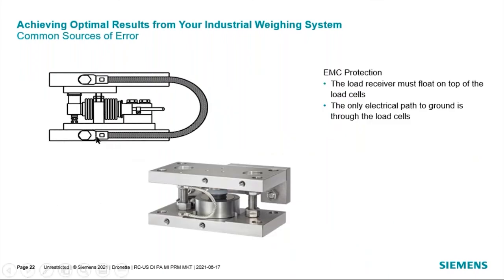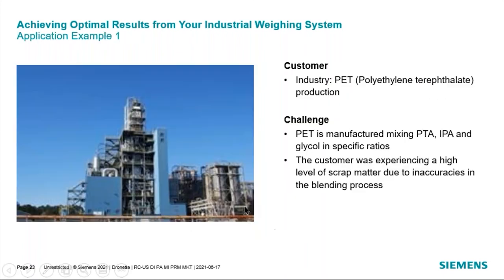You also want to protect the load cell from electrical noise. Because the vessel is floating on top of the load cells, the only path to ground from the bin is through the load cell — so you want a grounding cable. Also, if static electricity were to build up in or on the silo, the only path to discharge would be through the load cells, which could damage them. Mounting units typically come with a grounding cable to address this.